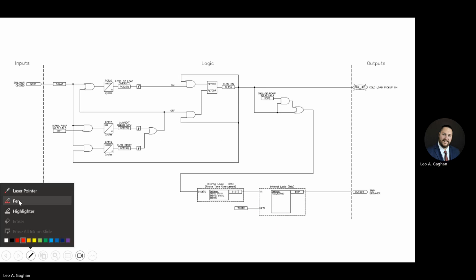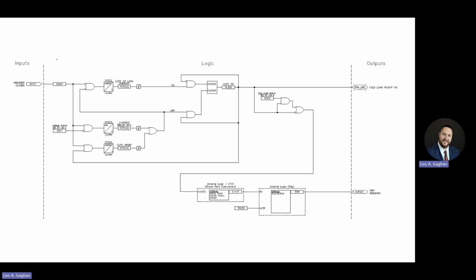So what we've seen for the current is this 50P1: the current went up with that cold load, and then as things start to warm back up, it slowly starts to drop off. And we've got that level right there, our 50P1. We've also got a 50P2, which will be up here. Because if the current's extreme enough, we do want to trip regardless of this cold load pickup logic. So that one was set at 1.4, that one's set at 1.9, just a bit higher.